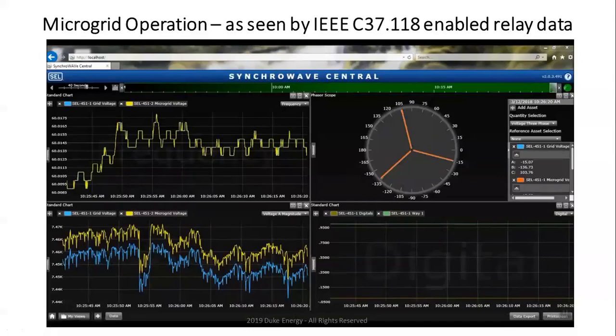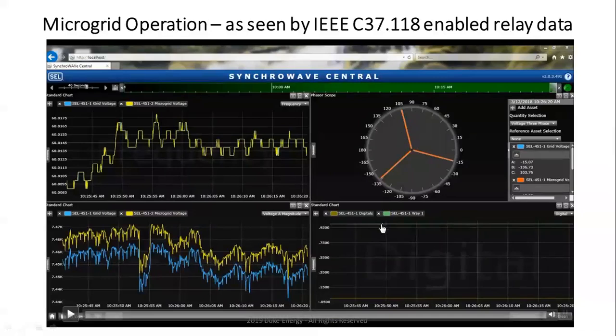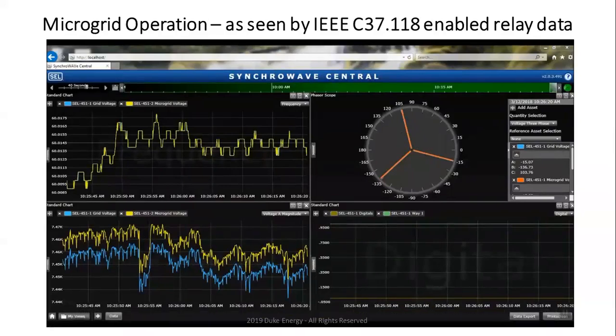But as you probably know, every time you build a PT, they have small inaccuracy, even though if you look at the numbers, they're all close to each other. On the bottom right, that's an angle difference between the grid and microgrid. And then on the top side, the green line, that's a PCC status, which is 1. And on the bottom, there's some kind of brown that says request to close.